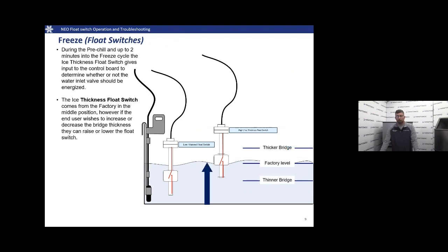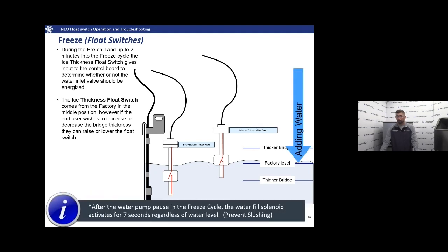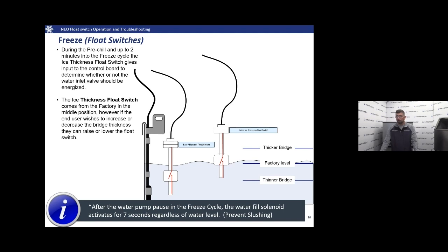The ice thickness float comes from the factory in the middle position — that's our standard setting. It's what we find will make a good thick sheet of ice with the proper eighth-inch bridge that we're used to seeing. The float can be raised or lowered depending on preference or the need in that area — one level up or down to thicken or thin out your ice. Note that you will see that water fill valve activate for seven seconds regardless of water level. That's to prevent slushing. Don't think that your float isn't working in those cases — it's part of the board.